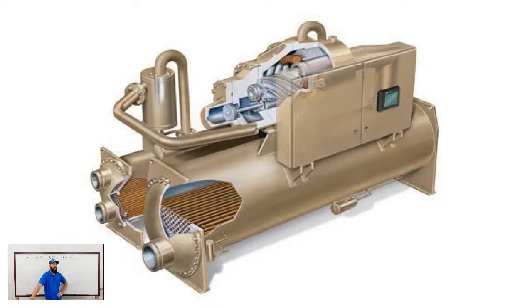Yes, absolutely. In the same way, we stage up by not being able to maintain, so the water gets too hot. As that water temperature begins to drop, both chillers are going to unload themselves. When the system recognizes that we're running at 44 degrees consecutively for X amount of time and both chillers have unloaded as much as possible, it's going to shut the lag down. Then as that chill water set point starts to creep back up, the lead chiller will ramp up with it and grab control of that load. It's the exact same control theory. It's no different.